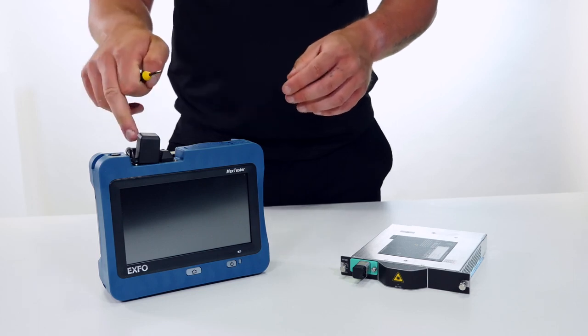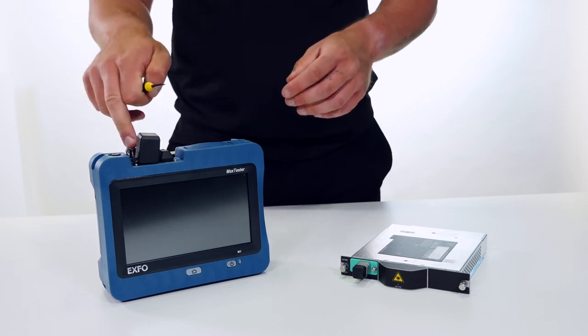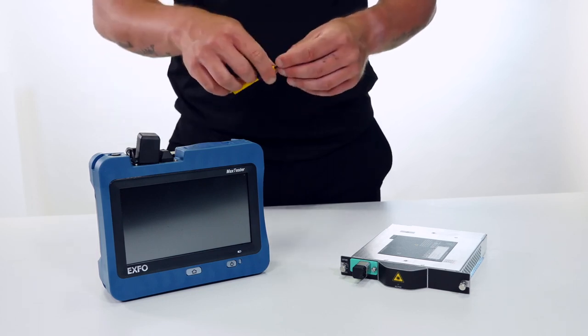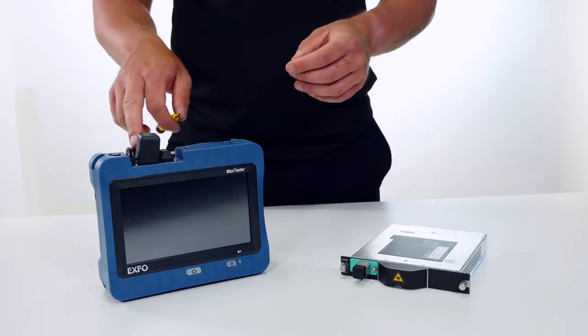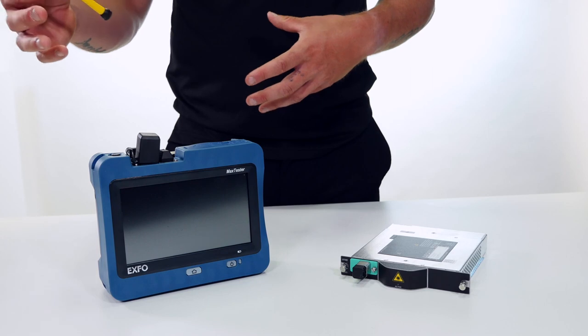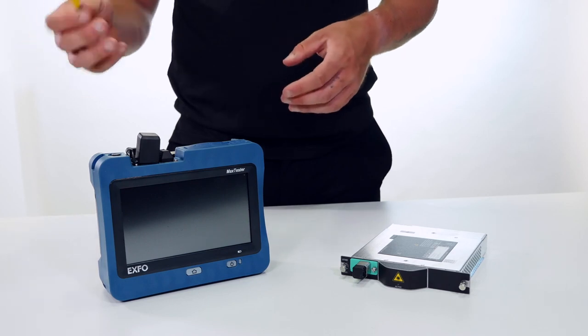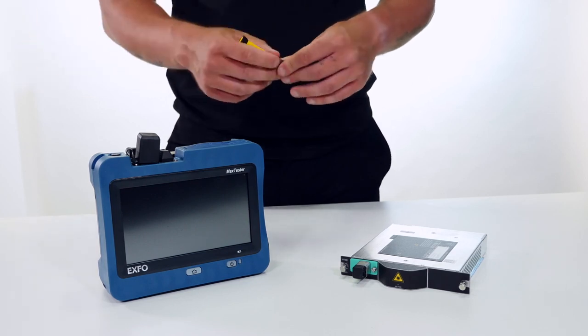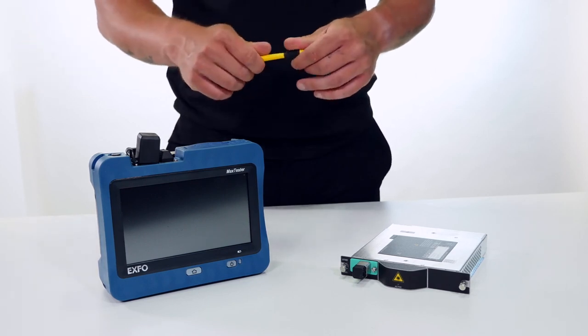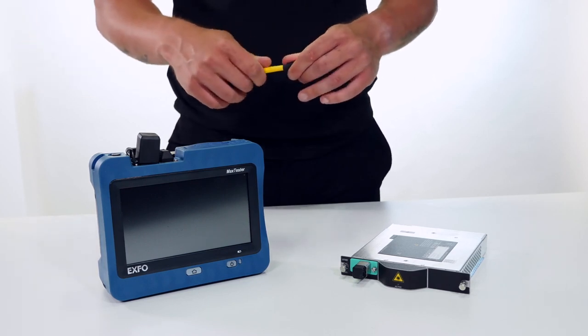If the internal connector becomes damaged, that's when we need to send the device into a service center to change and calibrate the internal connector itself.